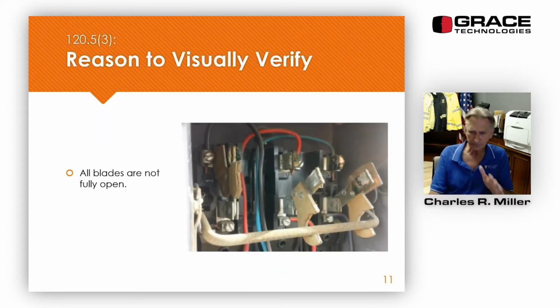Well, why do we do this? I've taught a lot of classes, and when I'm covering NFPA 70E for the classroom portion, we talk about this. If it is possible, we visually verify that all the blades are pulled out or the draw-out type circuit breaker is fully withdrawn, close to the front. I don't remember seeing myself one where a blade is still attached, but I've talked to a lot of electricians and maintenance people who have seen one, two, or all three blades still attached once the disconnect handle was pulled down into the off position.